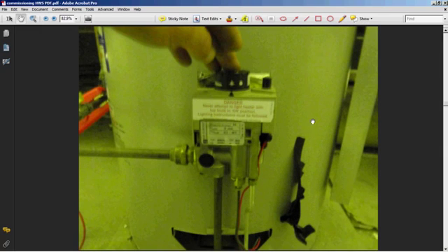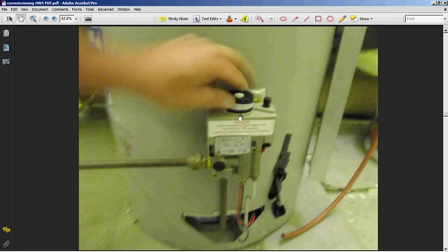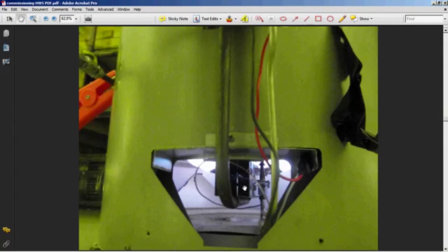First, before I connect the manometer, I always start the appliance first to get rid of any gas and air mixture that may be left in this pipe. What you don't want to do is connect the manometer, then struggle trying to light the appliance. It puts undue pressure in. So first you make sure it's on the sparker. Then push that knob down, and hit the ignition button. This will light the pilot light that's in turn heating the thermocouple. You then turn the control onto 5 or 6, so the main burner comes on.